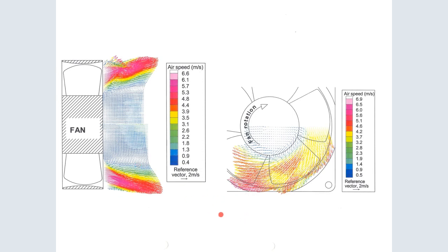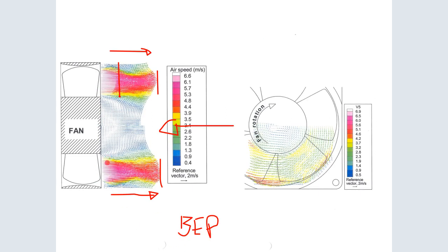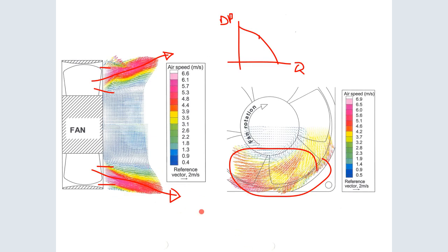Now moving off the best efficiency point — shifting to a higher pressure, lower flow region on the pump curve — we can see the angle of flow coming off is more tangential. There is a much higher tangential component and much less of the blade passage area is being used. Comparing the thickness of the jet coming off, it's much lower. So we have a lower flow rate coming through with higher tangential components, meaning the pump is now pumping less efficiently, even though it's running at the same speed.